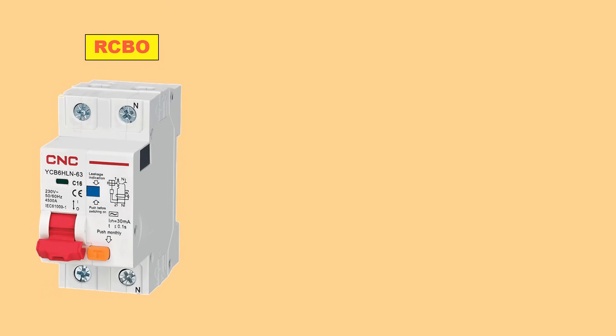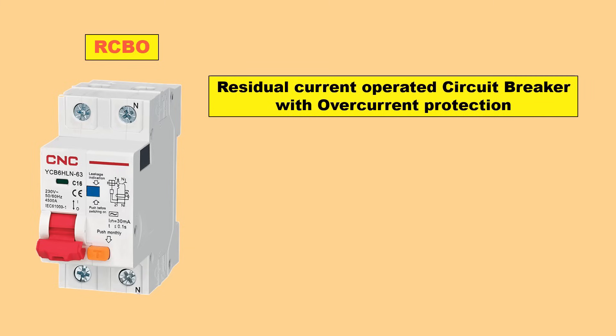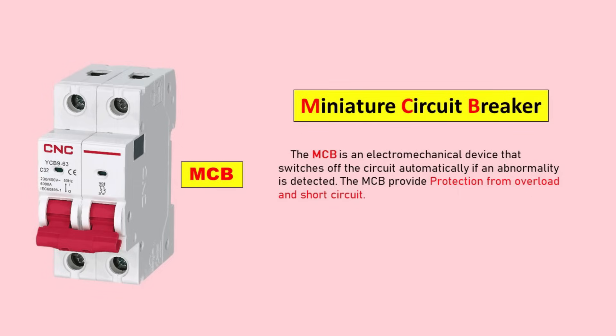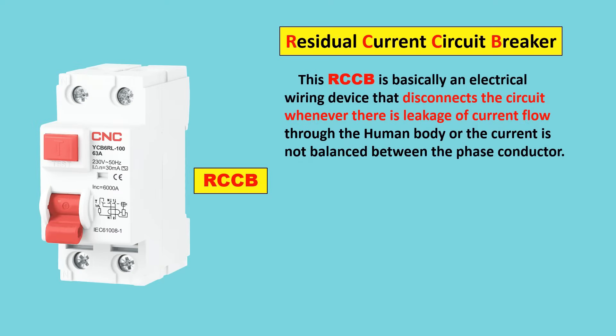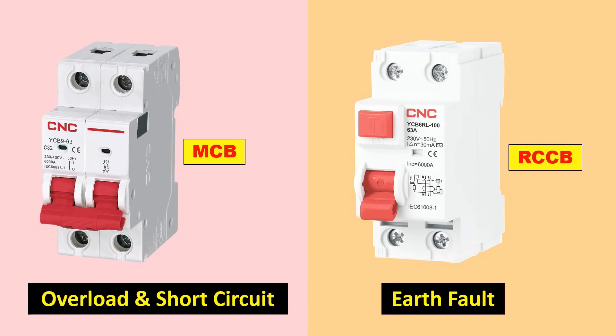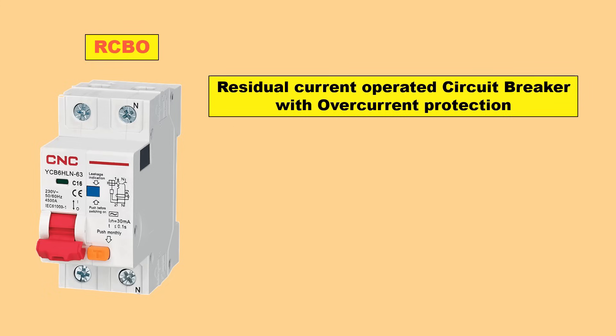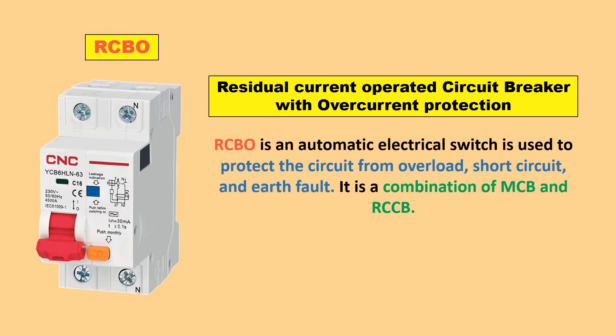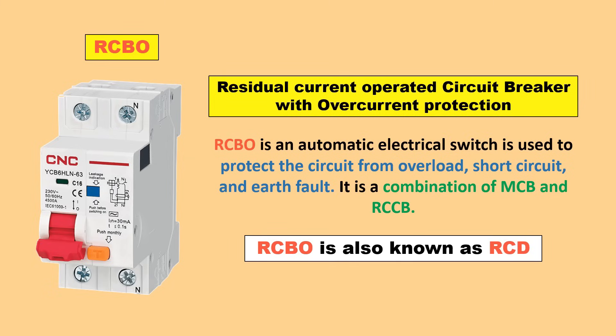Next device is RCBO. Full form of RCBO is Residual Current Circuit Breaker with Overload Protection. MCB provides protection from overload and short circuit, and RCCB provides protection from earth fault. If you want all three protections — earth fault, overload, and short circuit — in one device instead of using MCB and RCCB separately, then you have to buy a RCBO. This RCBO is also known as RCD, and they are not two different devices.